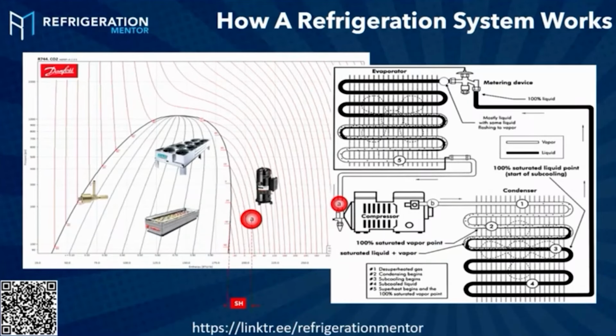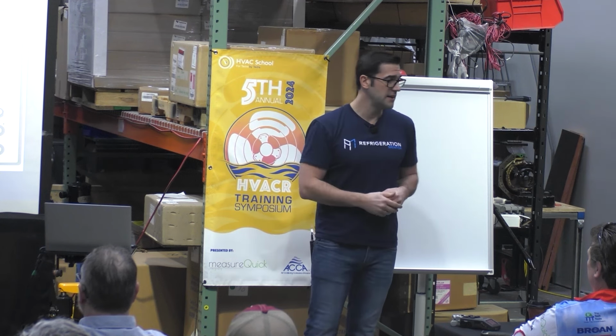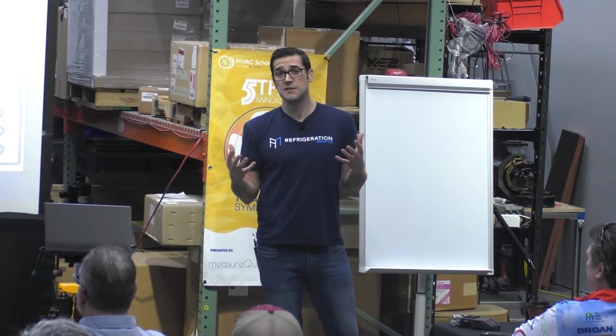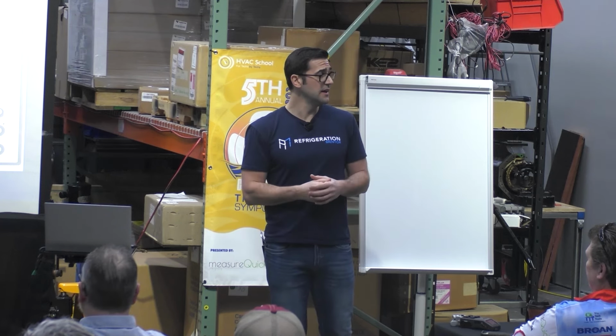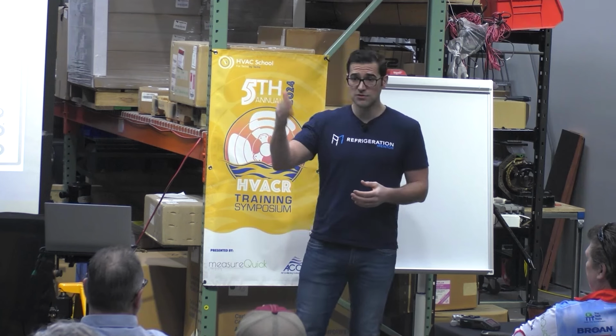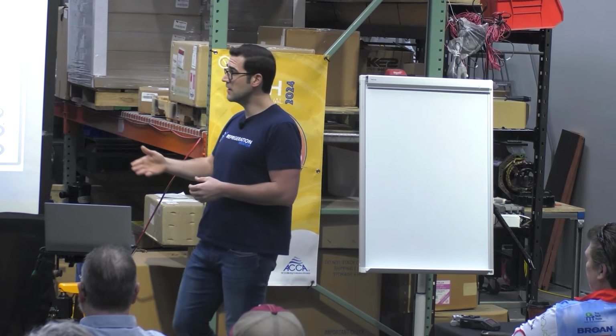Here's my mechanical system, there's my enthalpy diagram. So when I'm thinking about a system, when it starts, I always do the process of, okay, I've got power coming from the grid, or I've got solar power. There's solar power refrigeration systems. So I've got power coming from somewhere into the system. It goes to a breaker, it goes to fuses, goes to a contactor. That contactor doesn't start until there's some sort of control system that pulls it in and energizes it. And so that power goes through that contactor, and then it goes to a compressor.